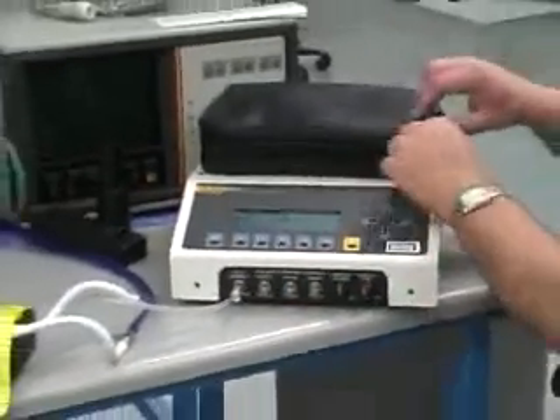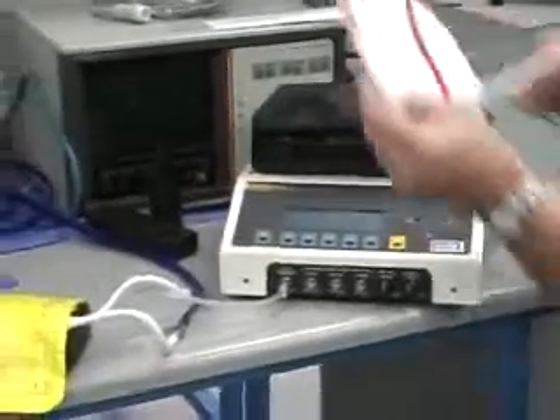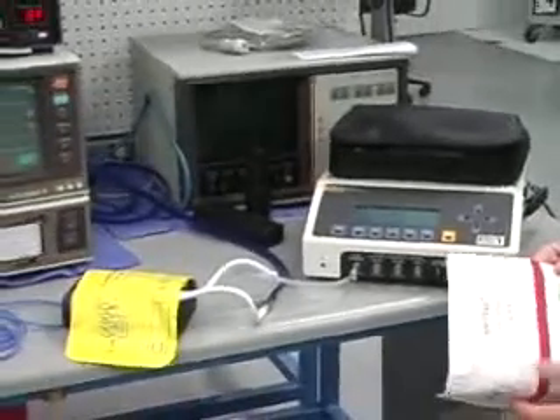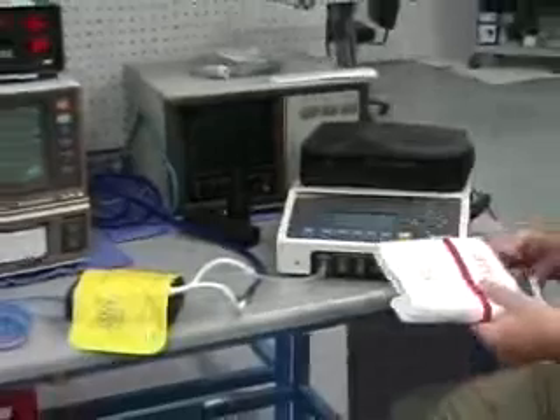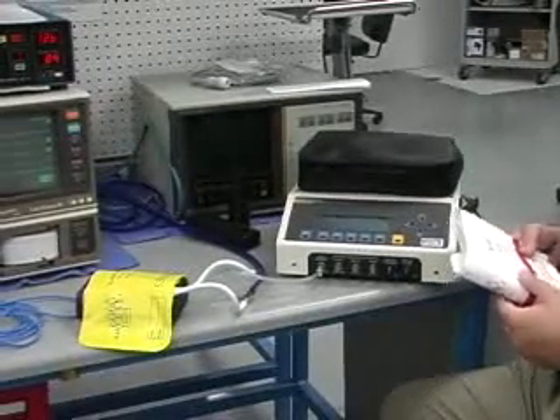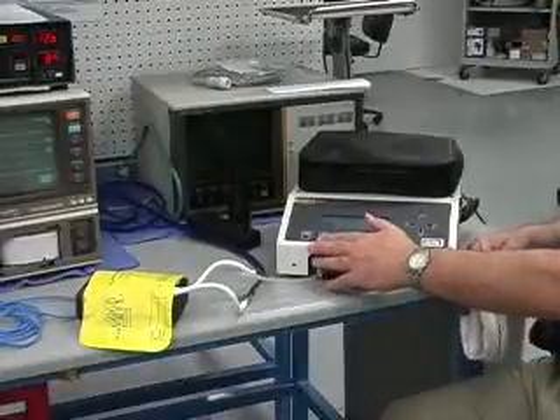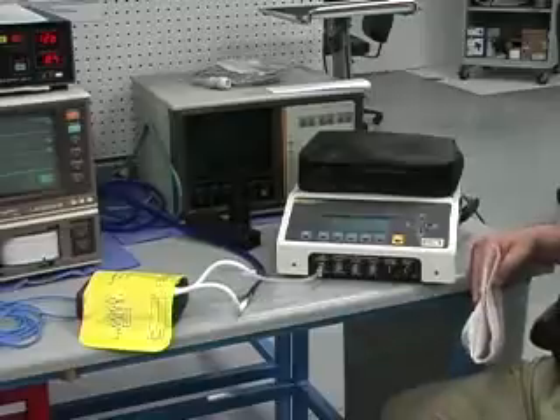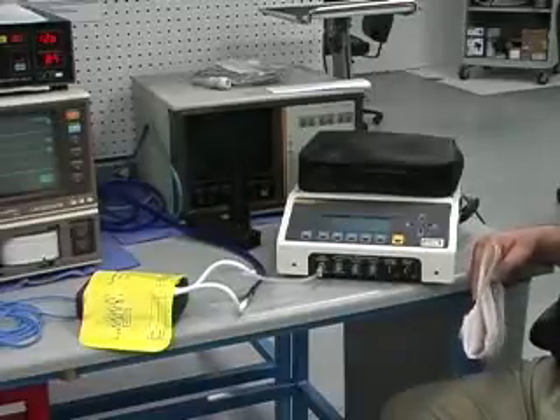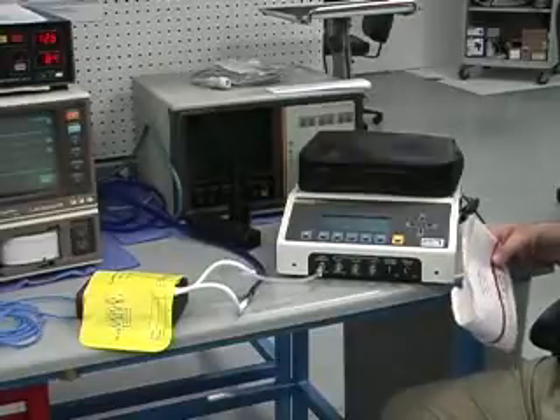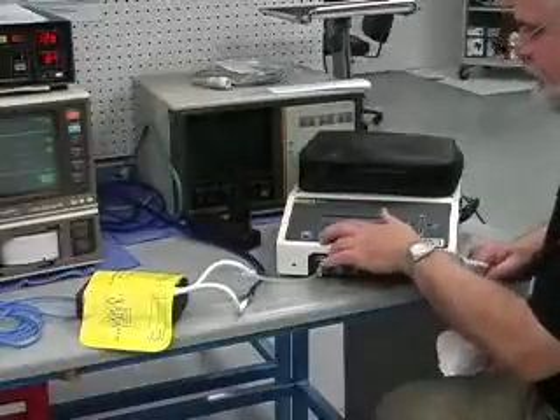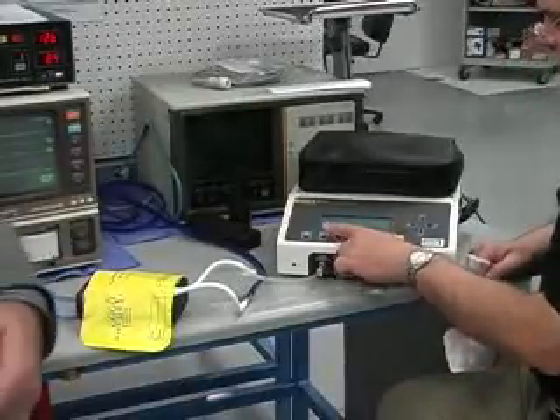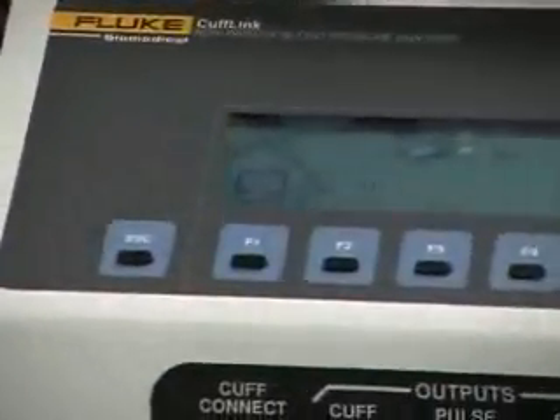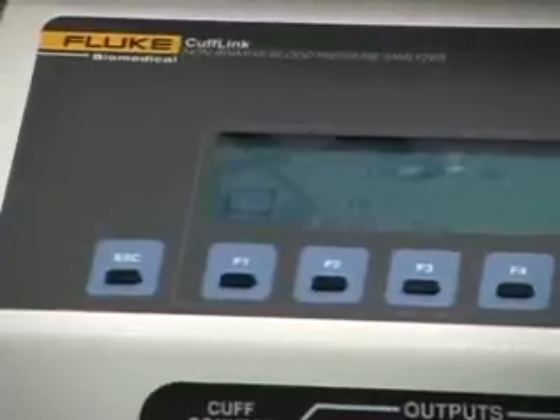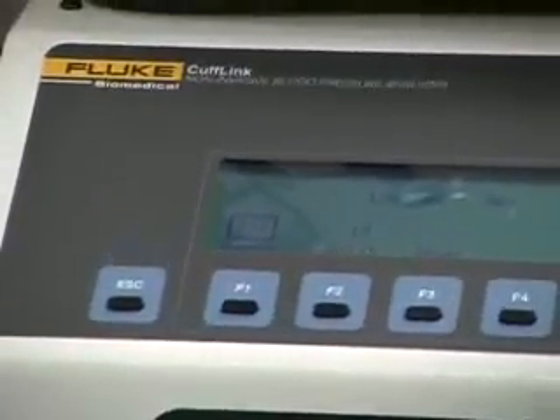Now, if you're going to try to run and do a large adult, or basically the large thigh cuffs that they use sometimes, it probably will still work fine, but you may just need to increase the gain or the amplitude of that pulse, because you've got a much larger artery in your leg, so it's going to be a much larger, higher amplitude pulse. So with it, you can go into the gain mode, as we have right here, and just simply increase that gain. And yes, about 110, 115% probably would be more realistic. And you would then be able to test your larger cuffs.